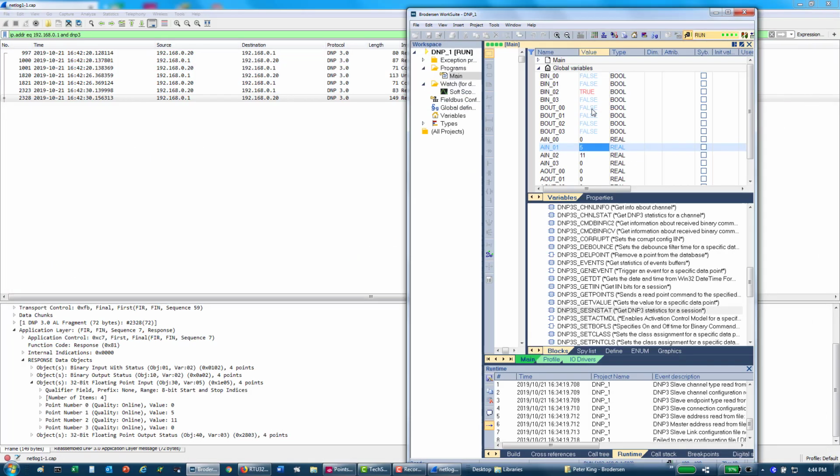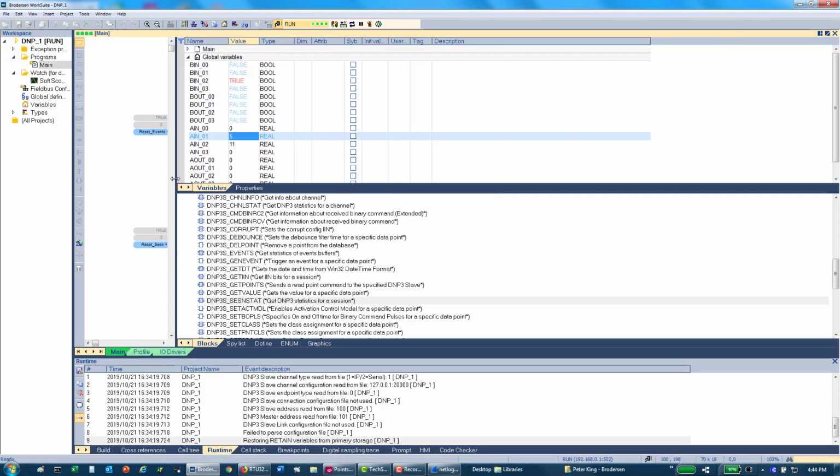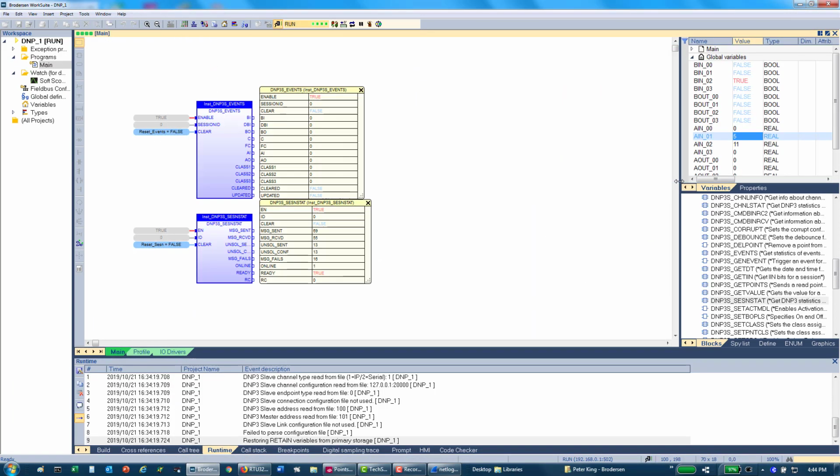So I'm going to stop Wireshark, just maximise this again so we get a better look at what's happening in the RTU. And this time we can see that there are messages being sent and received. If we just wait here for a sec, remember every 10 seconds we saw that the SCADA host was requesting data, so we just see messages received, messages sent. Wait another 10 seconds.